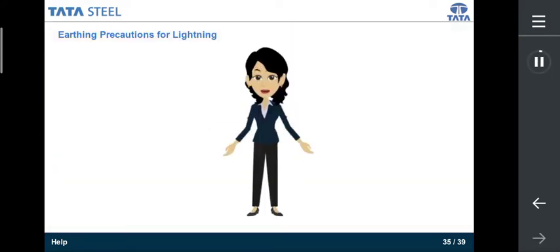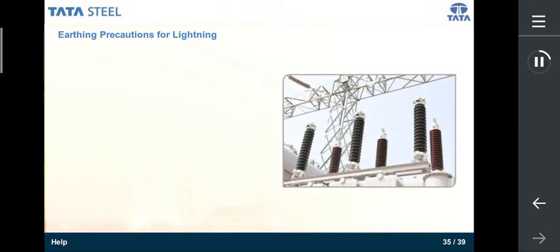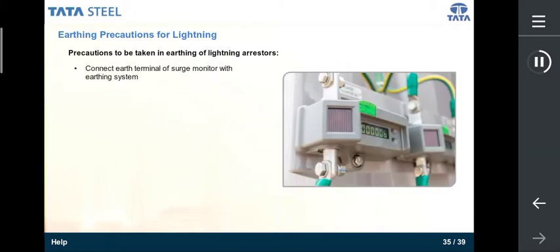Well, so we have learned many amazing facts about lightning. Now, when we talk about electrical equipment earthing, it is important to learn how lightning affects this equipment and how we prevent it from getting damaged. We know that all electrical power equipment has lightning arresters on it. They also need to be earthed. So, special precautions are needed for earthing of lightning arresters 132 kV and 33 kV fixed on the overhead lines. These are as given below.